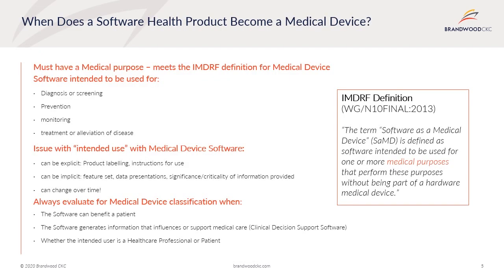The big question is: when does a software health product become a medical device? A software health product is considered a medical device if it meets the IMDRF definition. Software as a medical device, or SAMD, is defined as software intended to be used for one or more medical purposes that perform these purposes without being part of a hardware medical device. It must have a medical purpose. Put simply, if the intended use of the standalone software includes diagnosis, screening, prevention, monitoring, treatment, or alleviation of disease, it qualifies.